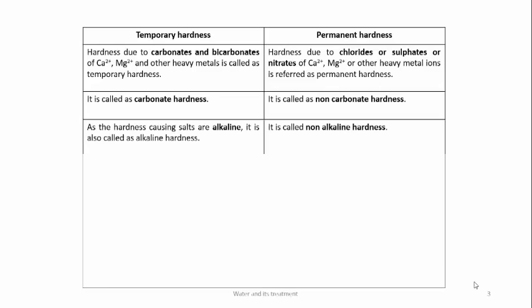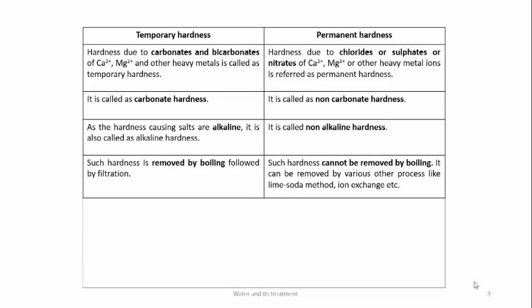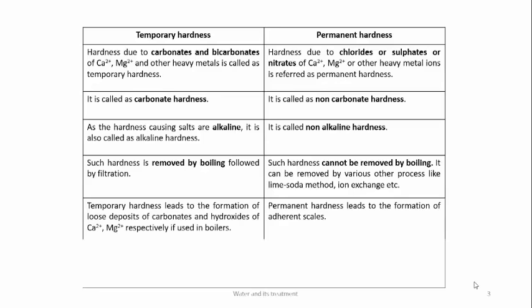Carbonates are basic in nature; therefore, temporary hardness is also called alkaline hardness, whereas permanent hardness is called non-alkaline hardness. Temporary hardness can be removed by boiling, whereas permanent hardness cannot be removed by boiling. Temporary hardness leads to the formation of loose deposits of carbonates and hydroxides of calcium and magnesium, whereas permanent hardness leads to the formation of adherent scales.